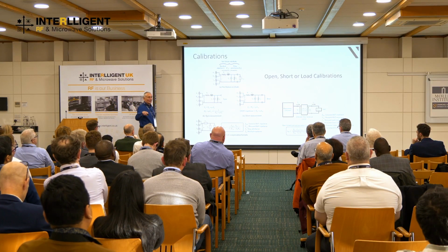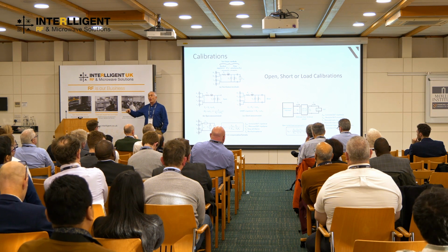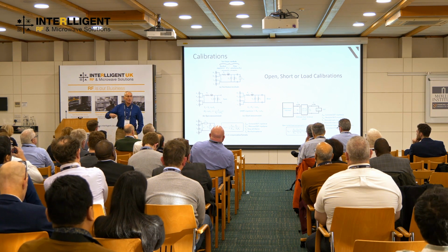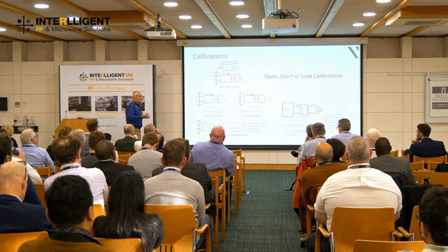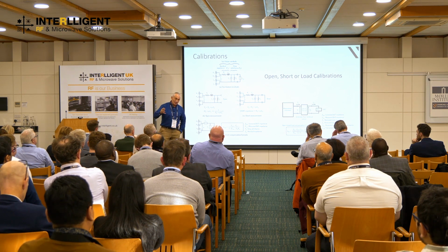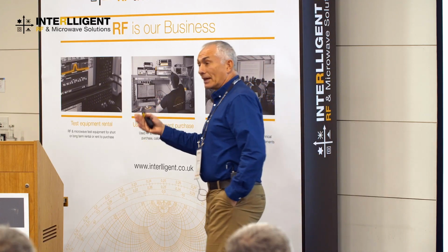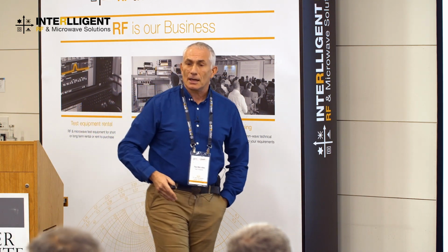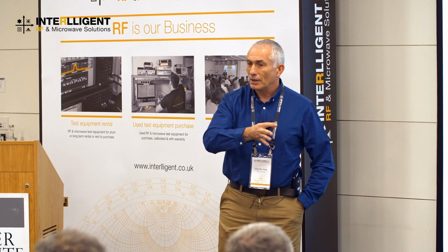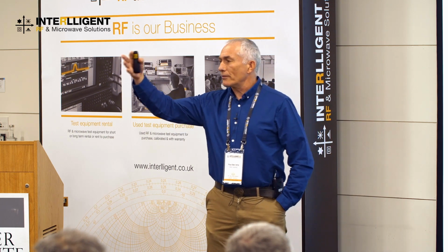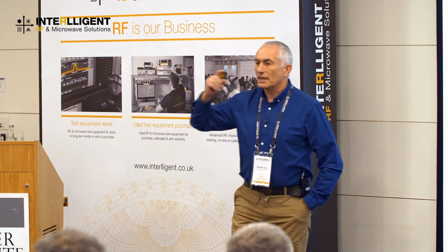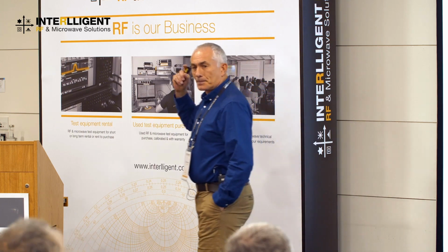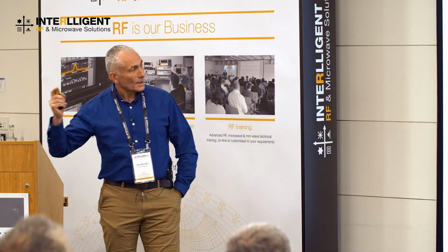Okay, so I mentioned that you have to calibrate out the effects of the line itself. Why? Because, what machines are we using? We're using LC meters, sorry, we're using VNAs. These are wonderfully great machines, fantastically calibrated up to their ports. Then you've got a line coming out to wherever your sample cell is, and you have to take out the effect of that line. But this is actually quite simple to do, and I like this.